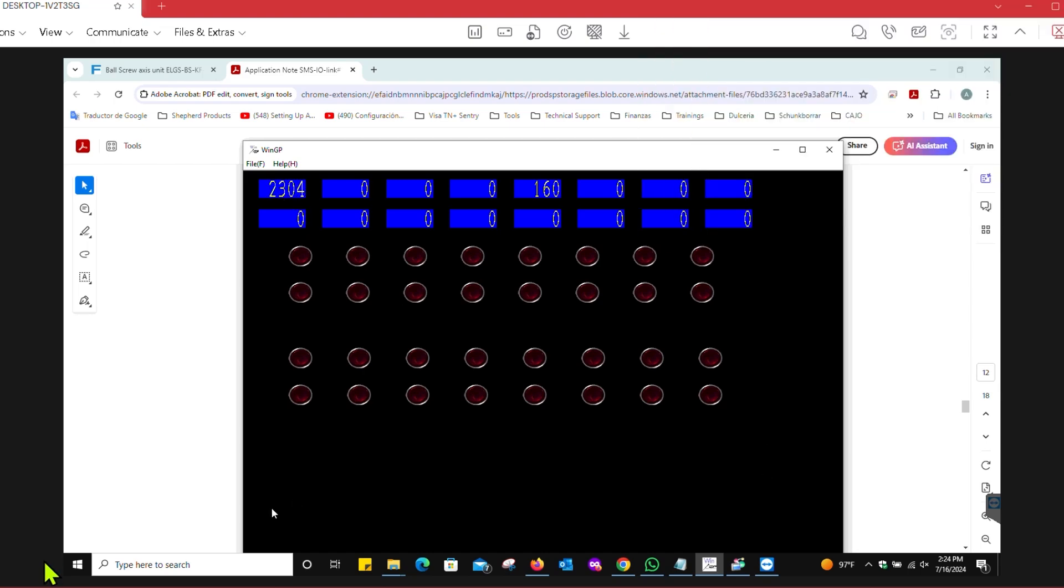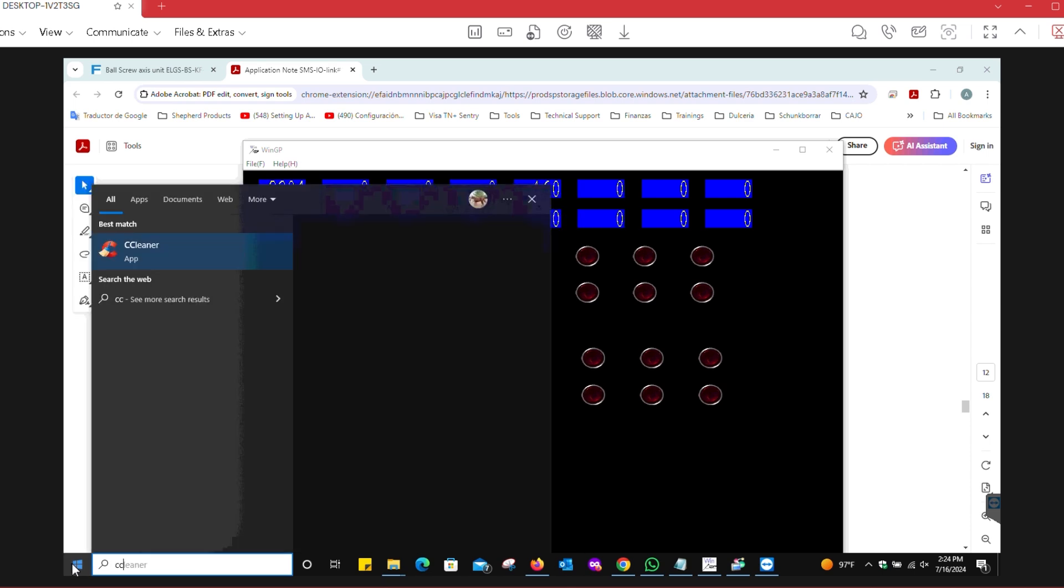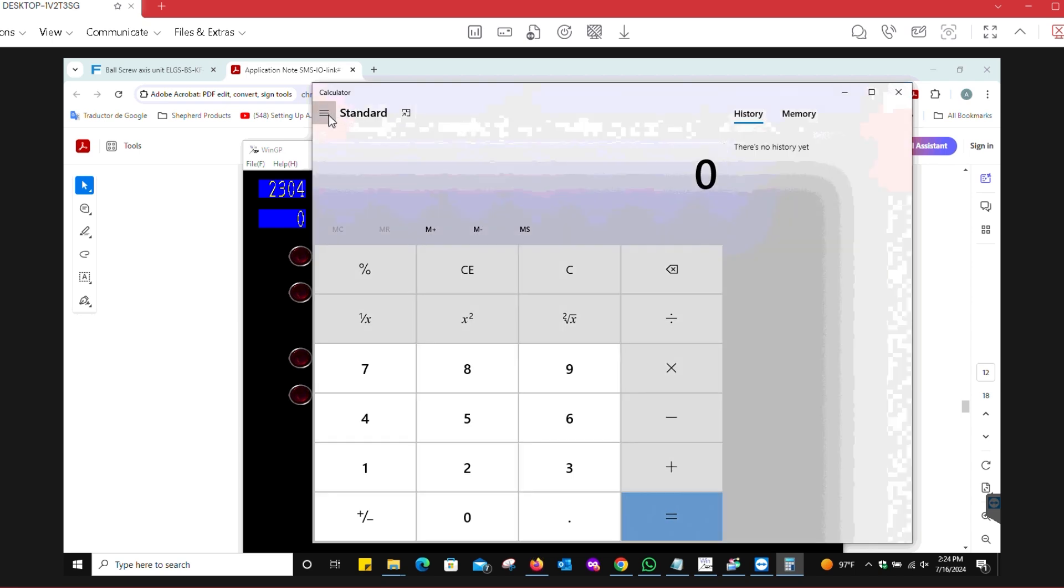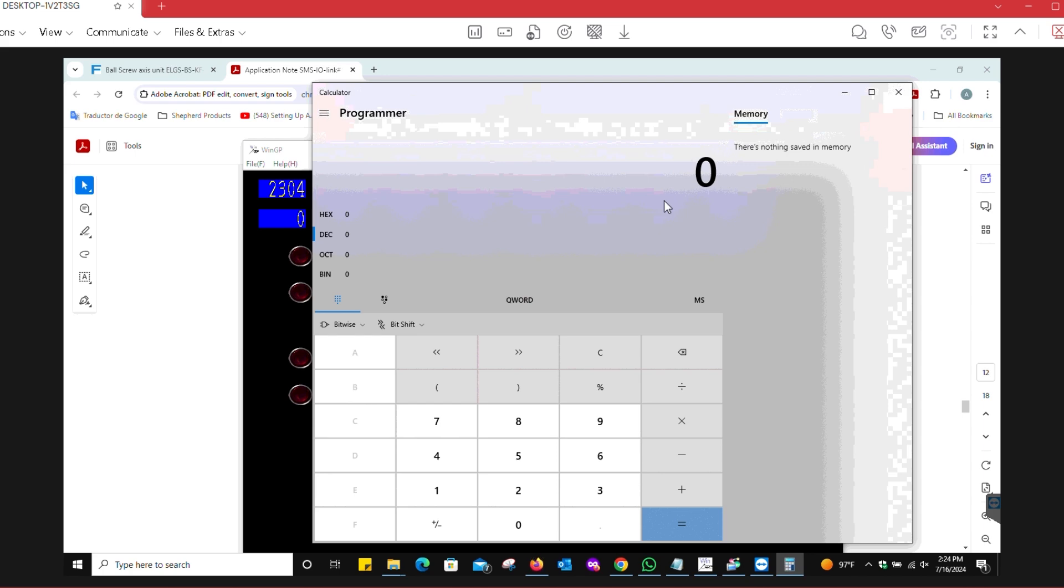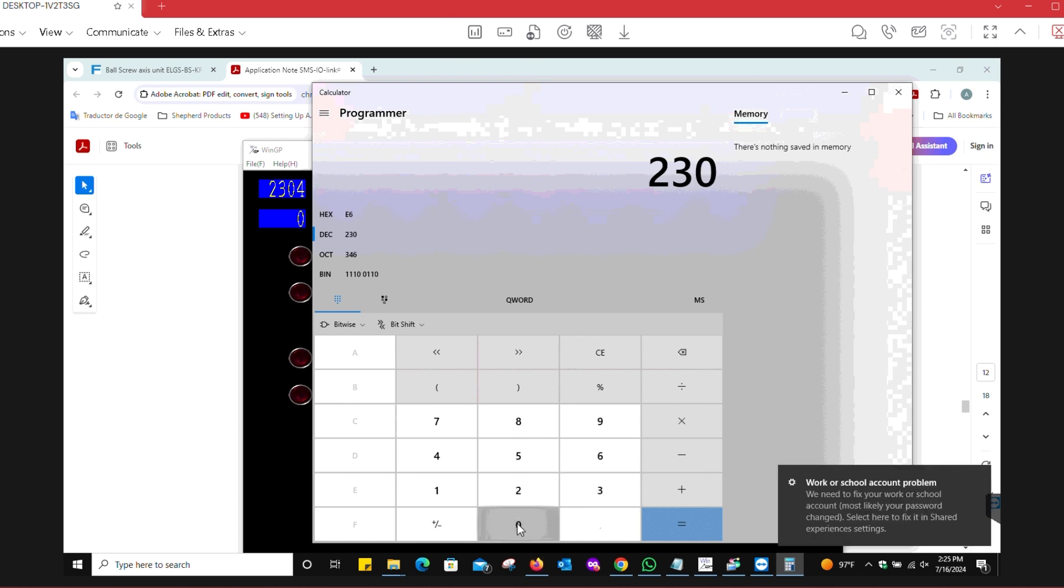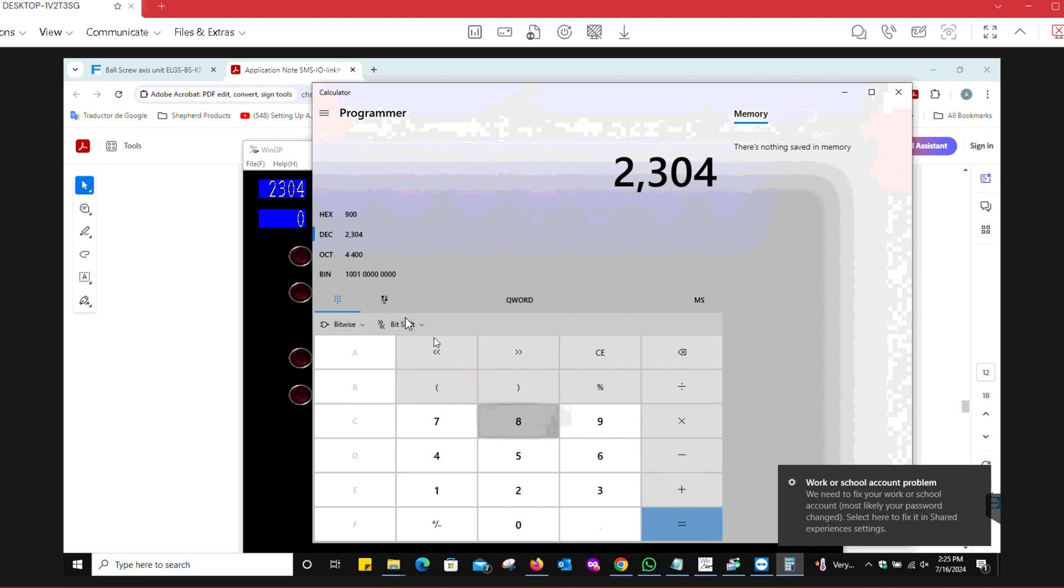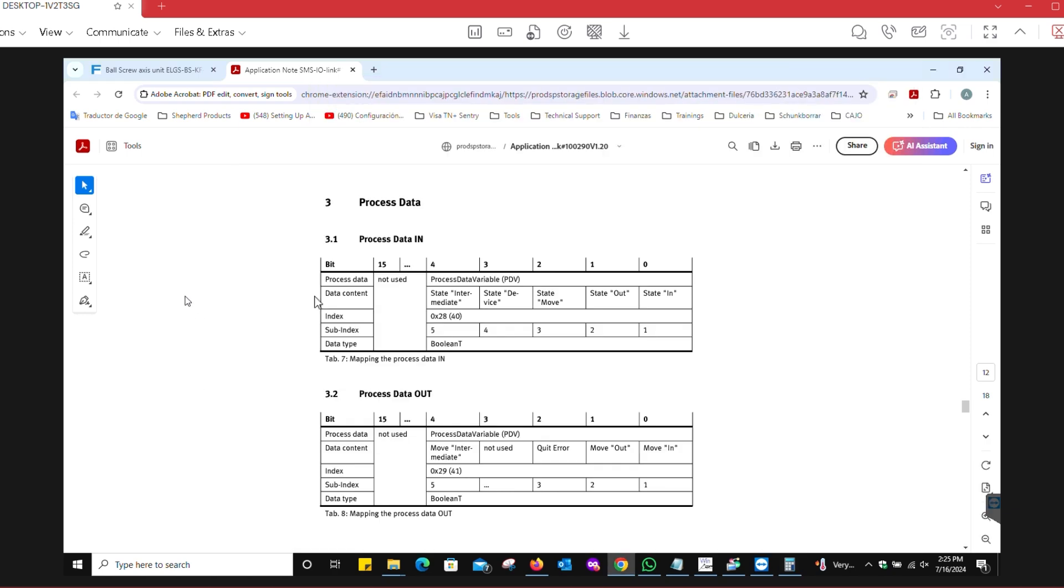If we were to open a calculator and go into the programmer mode and look at that number 2304, we see here - remember that the bytes are swapped, so this is actually the least significant byte here. We can see that the first bit is on, so bit zero and bit three. If we look here, bit zero says that the state is in, and I can physically see that the actuator is retracted. Bit three means state device, meaning there is a connection to the device.